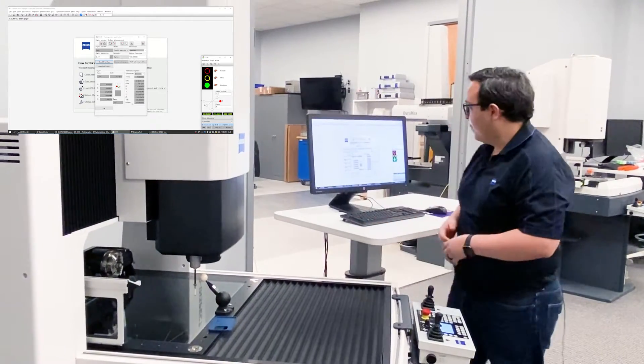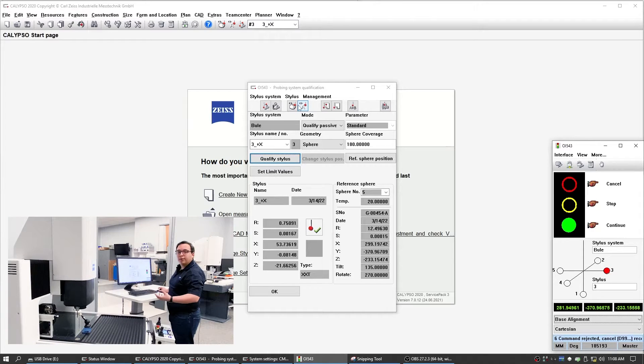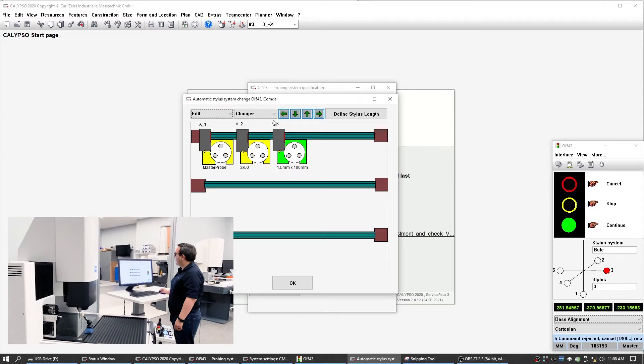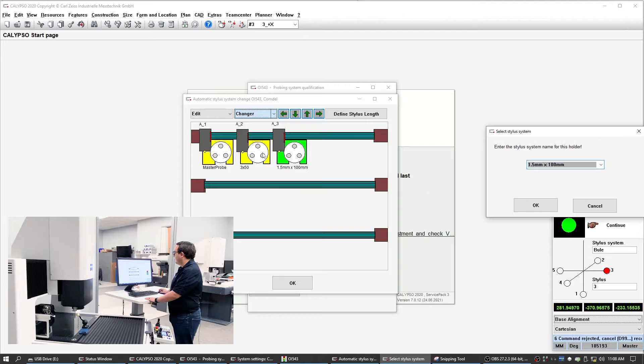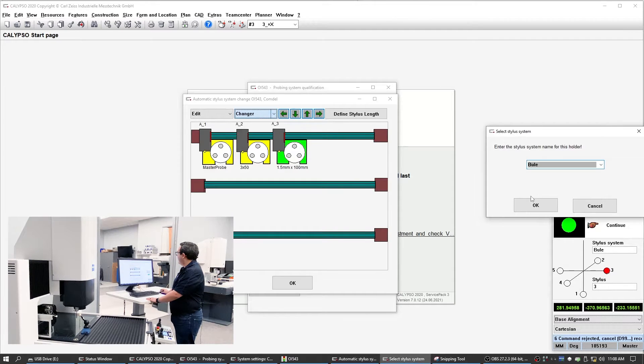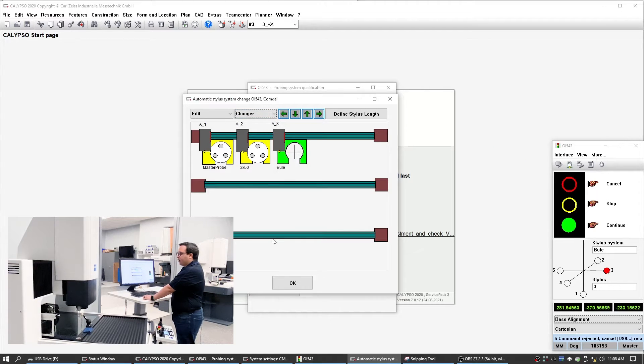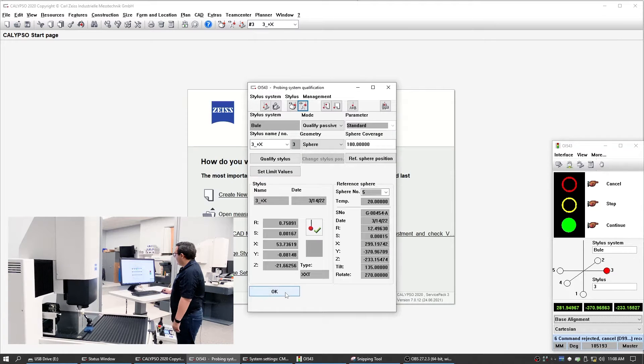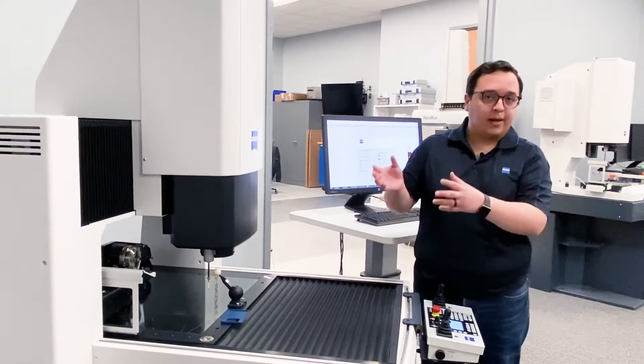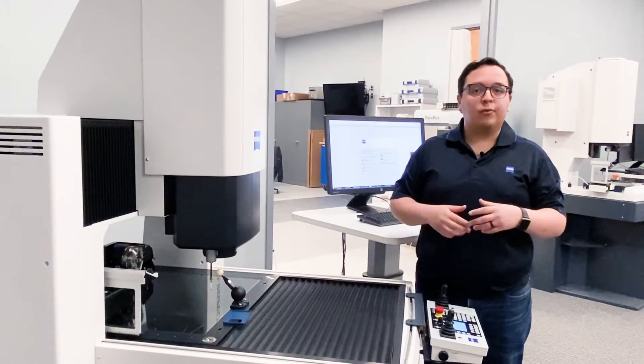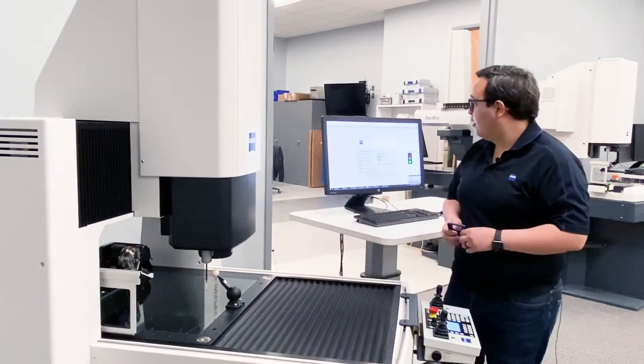So that it can run automatically. We already have the position of the rack — that's how we were able to put away the master probe — and all we have to do is assign the stylus to the correct stylus system. It's the misspelled 'blue' — I'll change that name later. And it can be put away when it needs to if we're going to use the vision system at all.